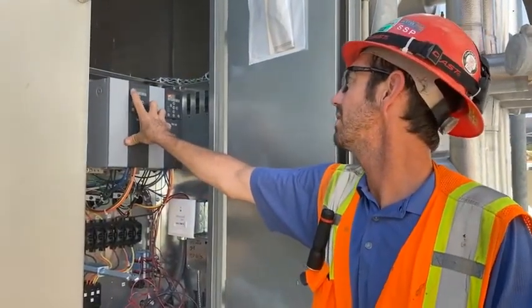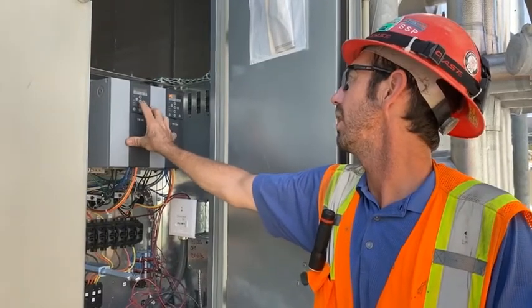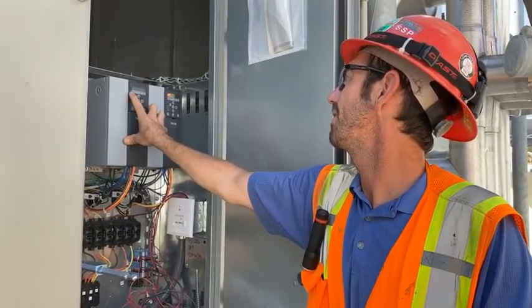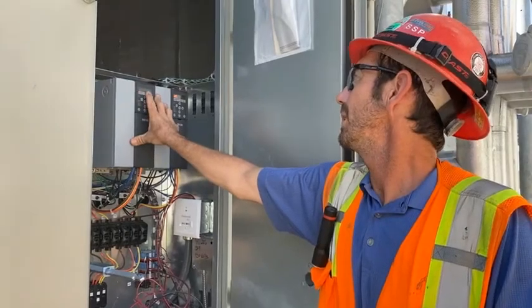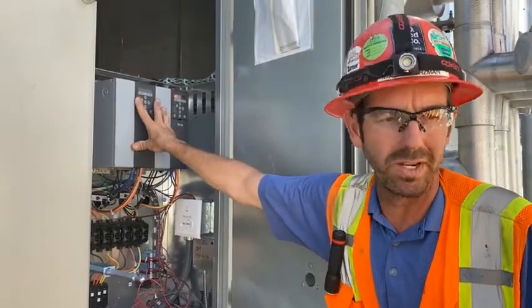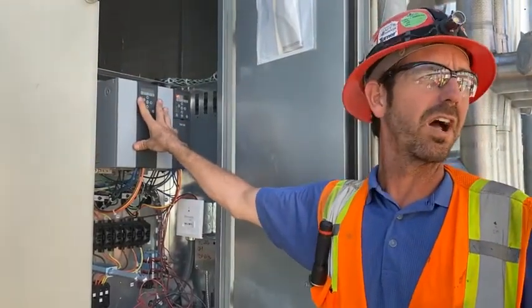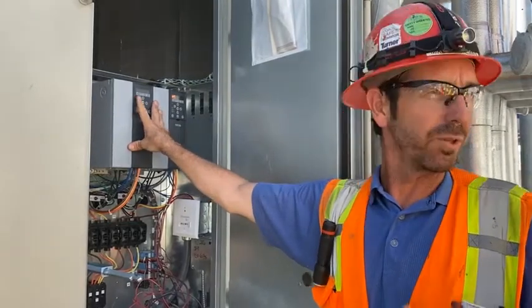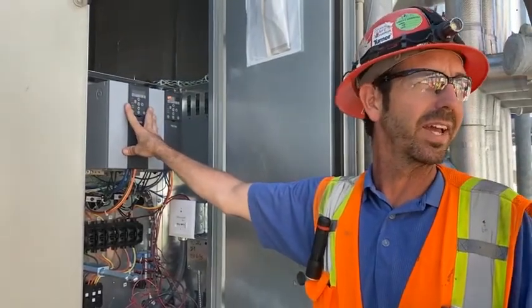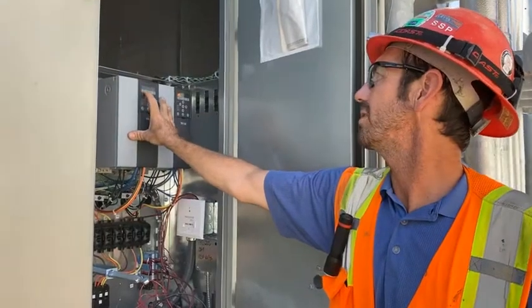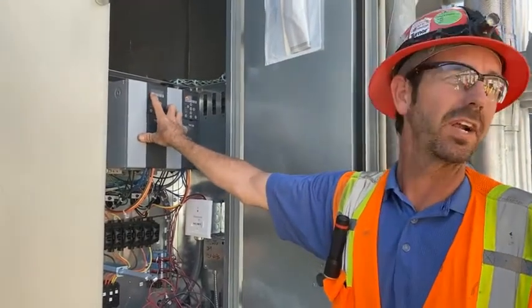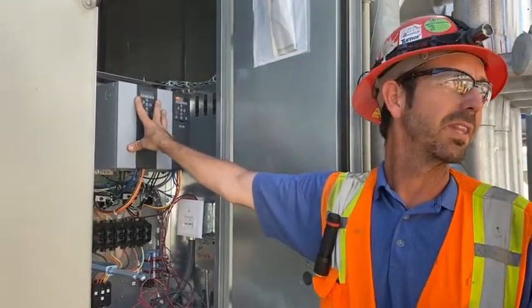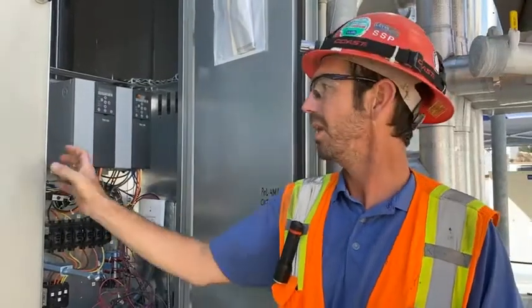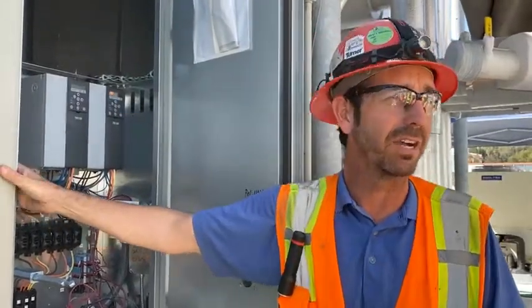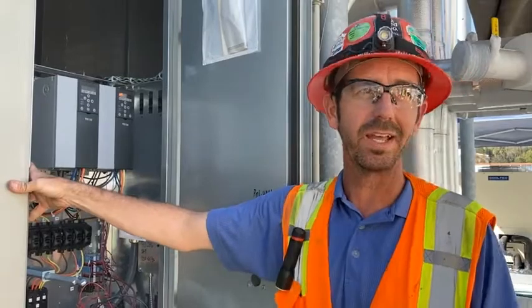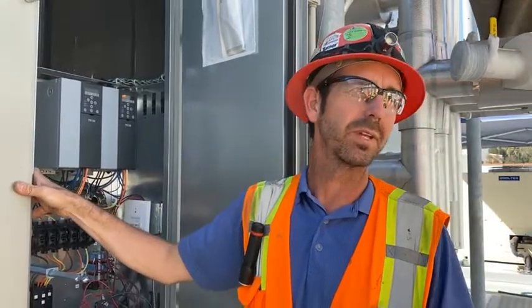So limits, motor limits 4-1, that's what I was talking about. Right now we have motor speed low limit. So this fan, we don't want it to spin lower than 20 hertz when it's turned on. Anything lower than that can ruin the motor, and it can also cavitate the fan. So 20 hertz is the minimum. 73 hertz is the maximum we can spin this motor, to get us the proper CFM at a full load cooling situation. Every box is wide open, max cooling. 73 hertz.